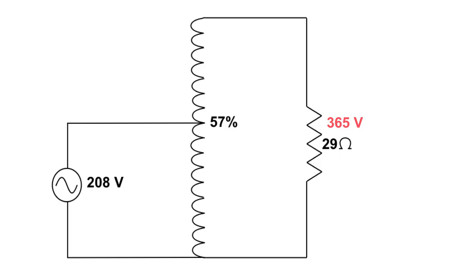Next step is to get the current at the load. And just like before when we had the step-down autotransformer, we're going to take the voltage, divide it by the ohmic value of the load to get the current at the load. That works out to be 12.6 amps. So we've now determined the voltage at the load. We have the current at the load.